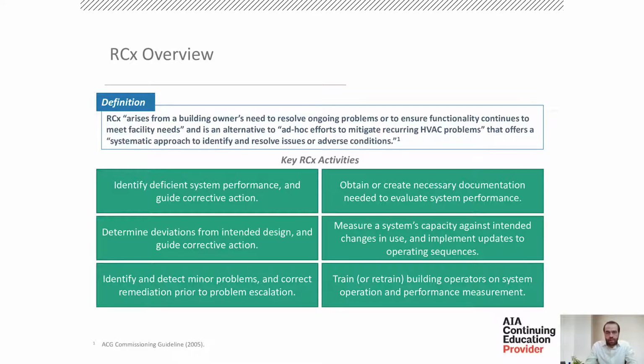Fourth is obtaining or creating the necessary documentation needed to evaluate system performance. As you might glean here, if the design of a system is changing, if the operation of a system needs to change, the retro-commissioning agent needs to be able to define those changes and then write the test procedures for those particular changes.